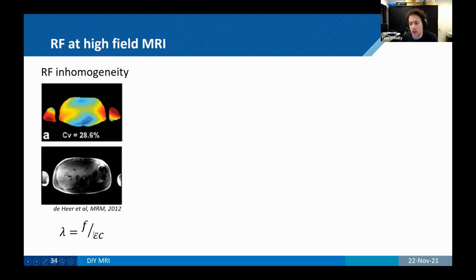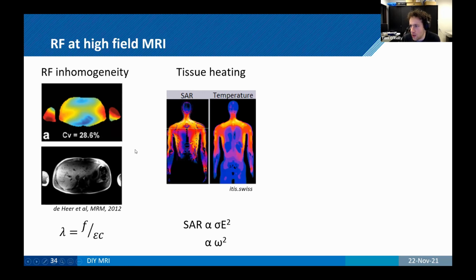And that's because of the wavelengths that we're dealing with at 3 Tesla. 3 Tesla is on 126 megahertz, I think, or 120 megahertz. The wavelengths are quite long in free space, but because the wavelength scales with the epsilon, the permittivity of the human body, in the anatomy it's actually quite short. And as that wavelength approaches the dimensions of the human body, you get these kind of standing wave-like effects. So at high field, it's very hard to get homogeneous RF.